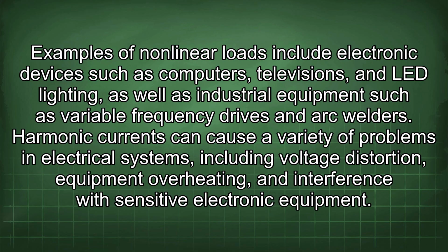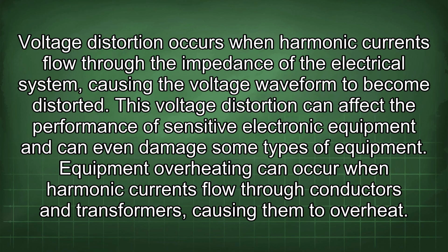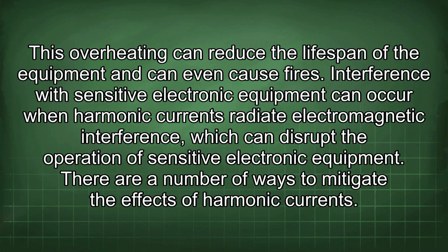Harmonic currents can cause a variety of problems in electrical systems, including voltage distortion, equipment overheating, and interference with sensitive electronic equipment. Voltage distortion occurs when harmonic currents flow through the impedance of the electrical system, causing the voltage waveform to become distorted. This voltage distortion can affect the performance of sensitive electronic equipment and can even damage some types of equipment. Equipment overheating can occur when harmonic currents flow through conductors and transformers, causing them to overheat. This overheating can reduce the lifespan of the equipment and can even cause fires.